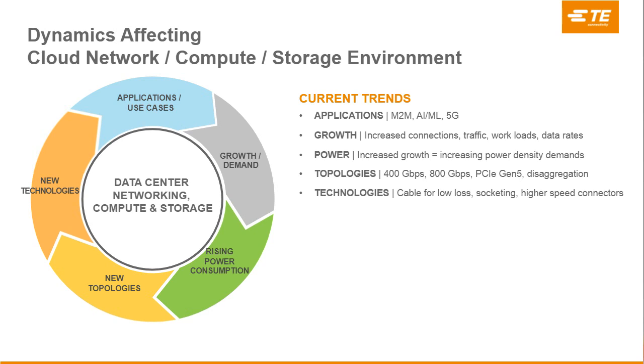Let's talk about the performance of this. Now, we just touched base on the less land mass that it takes. Well, you still have to accommodate the same amount of racks and cabinets inside the data center. So instead of going horizontal, they're now going vertical. And some data centers, typical, are going to be 2, 3, maybe 4 stories. There's now designs and infrastructure to go 8 stories tall. That's going to cause more megawatts needed to be used. And we're already seeing a transition from owners going, for example, from 30 megawatts per building to 60 megawatts per building. There's some instances where we're seeing 100 plus megawatts per building.